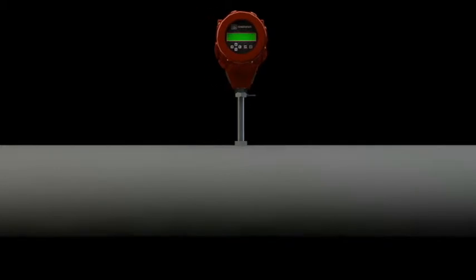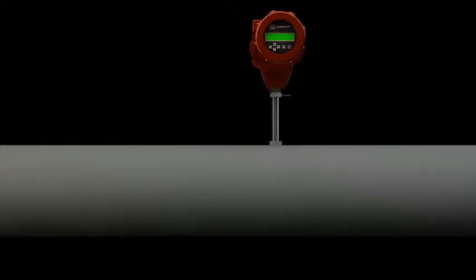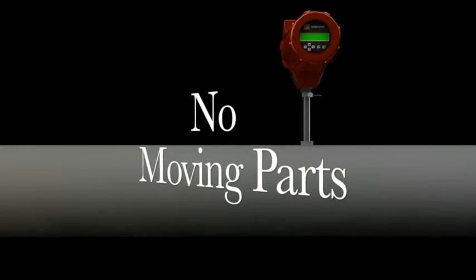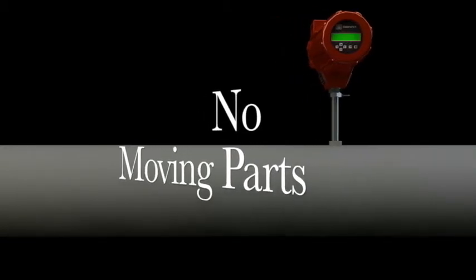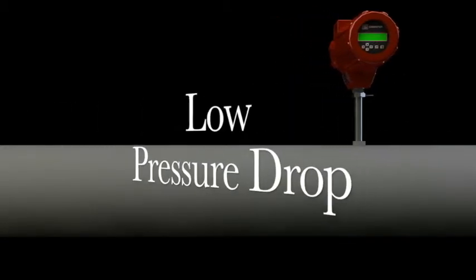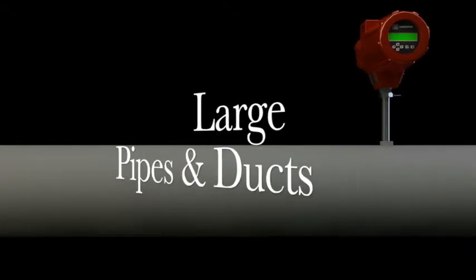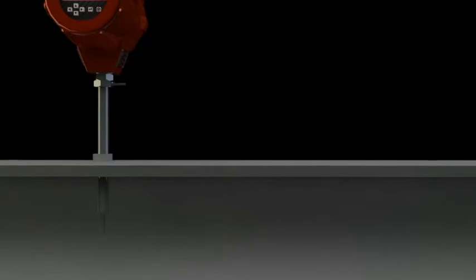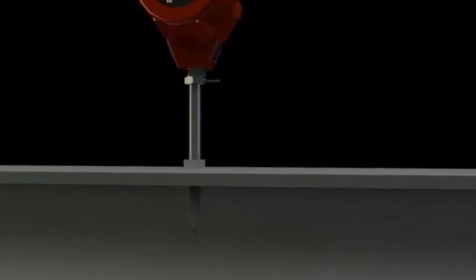with the same instrument. Since they are rugged and reliable, have no moving parts, are easy to insert via hot tap, have negligible pressure drop, and offer an economical solution to large diameter pipes and ducts, thermal technology has been rapidly adopted over the last decade. So, how does this amazing technology work?